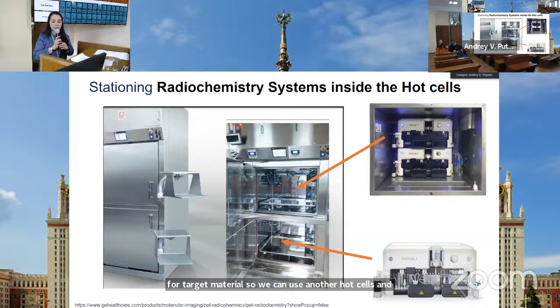This system uses single-use materials. And for aseptic processes, we have sterilization filtration, and inside the dispensing kit, we can use the sterilization filters, position 6 on this schema. This dispensing system is very useful because we don't have any manual operation. All operations are done with a computerized system.